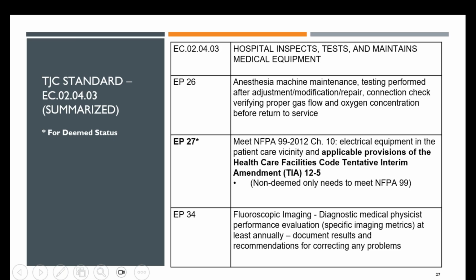On this slide for EC.02.04.03, it shows that you should perform maintenance and testing on anesthesia units. This is really important to separate out after any adjustment, modification, or repair, and before returning the anesthesia units to service, each connection is checked to verify proper gas flow and oxygen concentration. You also need to meet NFPA 99-2012, Chapter 10 for electrical equipment in the patient care vicinity.